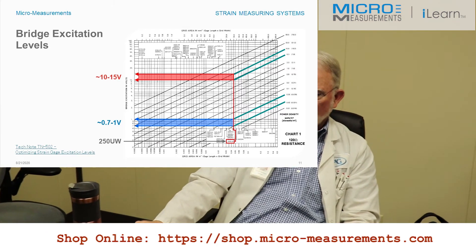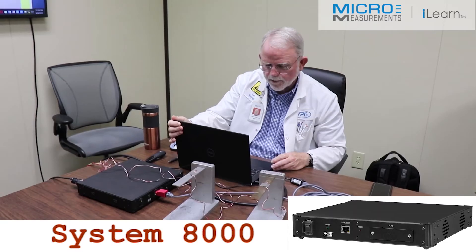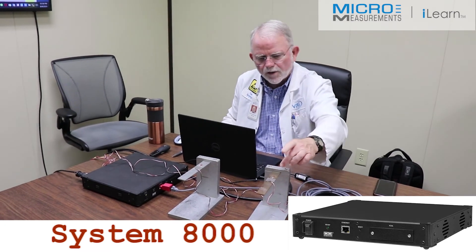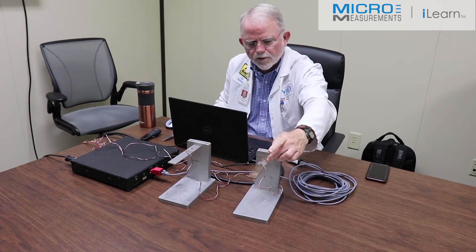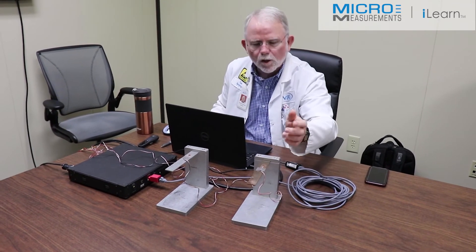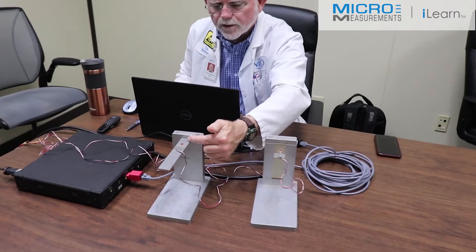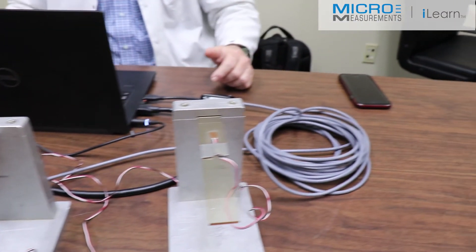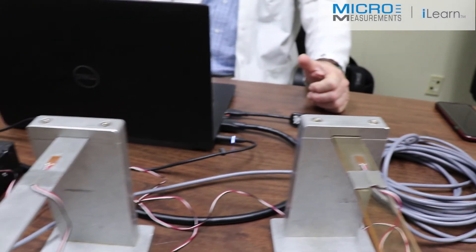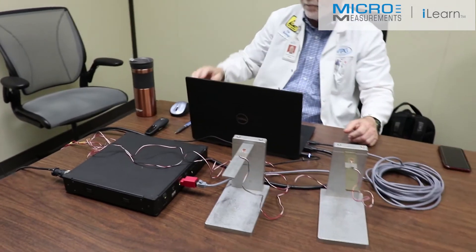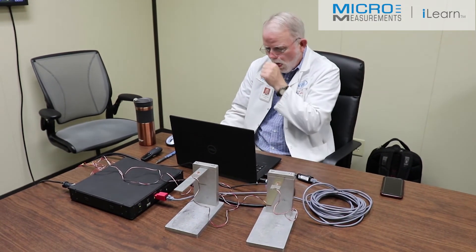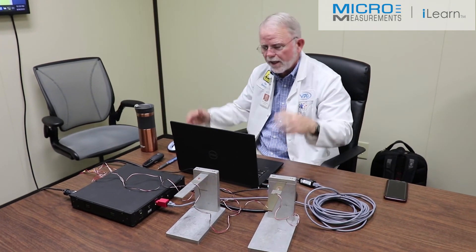If you overheat the strain gauge, you will make it go unstable — it typically drifts off in the positive direction. I have set up a demonstration of grid self-heating. I've got a beam with a 250 thousandths active grid gauge, 120 ohms, on a piece of polycarbonate — a poor heat sink — and the very same strain gauge bonded to aluminum, which is an excellent heat sink. The difference between them will be the grid self-heating. I'm also hooked up to the System 8000 and using a LabVIEW program. I'm going to connect to the scanner, zero the channels, and then look at the graph.